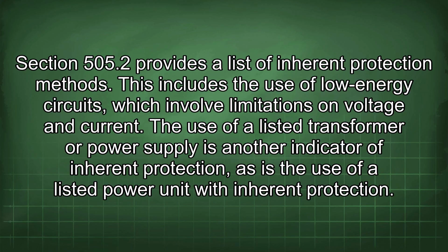This includes the use of low-energy circuits, which involve limitations on voltage and current. The use of a listed transformer or power supply is another indicator of inherent protection, as is the use of a listed power unit with inherent protection.